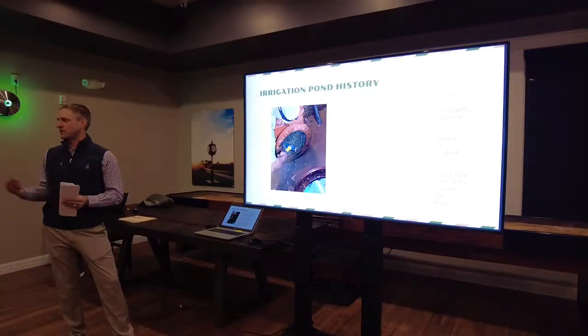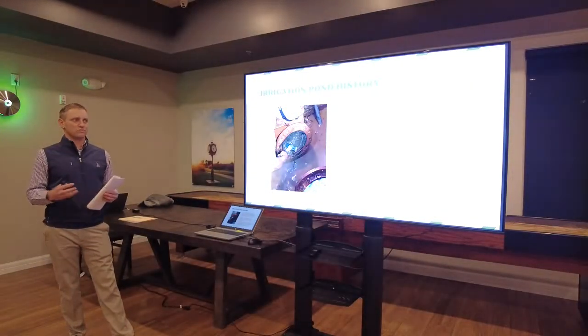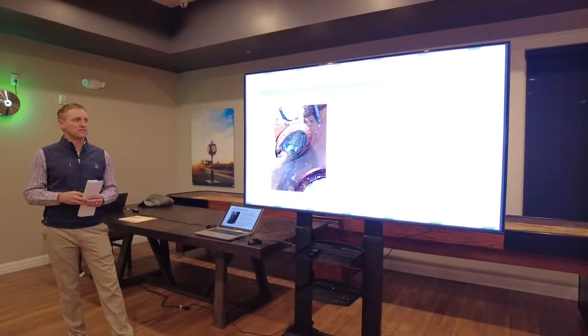And we do what we can through this summer. Here, this is when they took apart the intake. As you can see, there's sludge buildup and grime that goes into the intake. We have no strainers, filters, or waste strainers to pump out any excess silt and sands from getting sucked in. So the pumps are just at the mercy of what allows it to flow through.